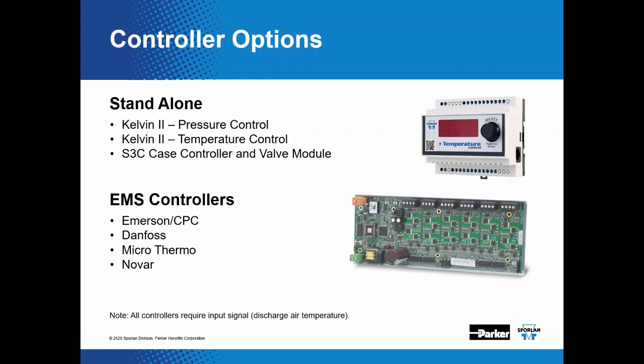Regarding controllers, Sporlan offers a standalone controller to drive the EEV and the electric EPR. Here are some examples: the temperature control and pressure control in the Kelvin series, and also some case controllers as well operate as standalone controllers. More commonly, EEVs and EEPRs are controlled by dedicated boards or case controls that communicate with the store's BAS, building automation system. This allows the technician to see and monitor case temperature, valve position, and the list goes on. And this can take place from the controller or from even a remote location.